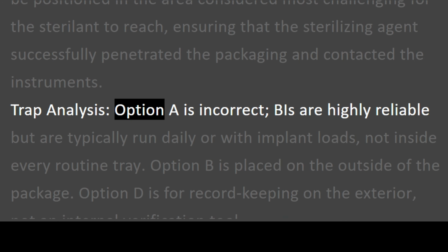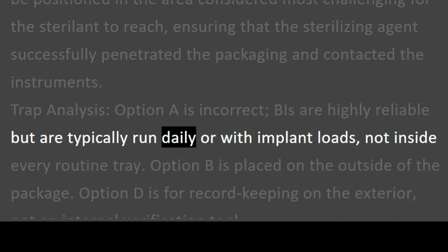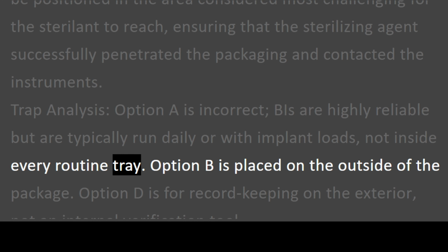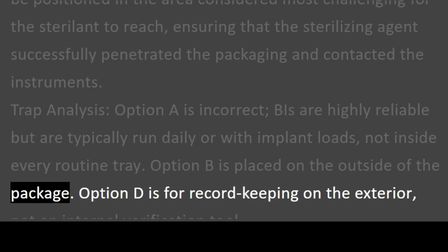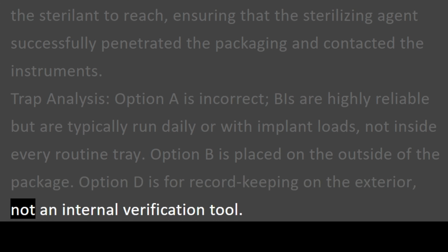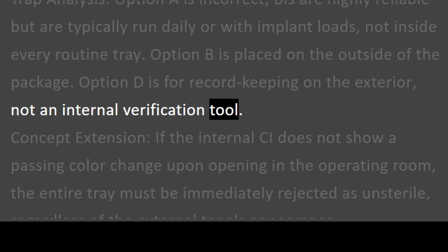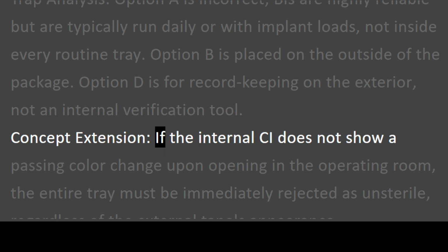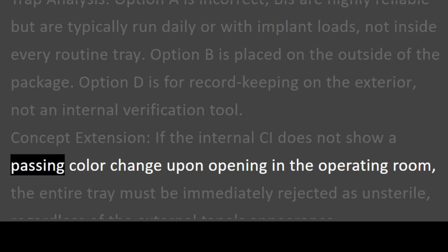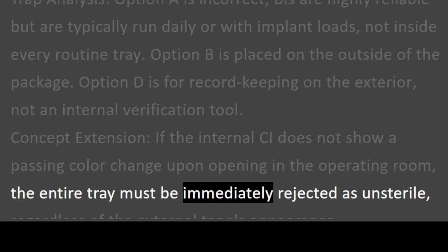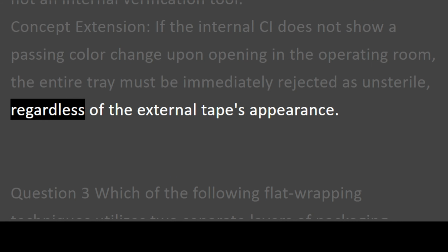Trap analysis. Option A is incorrect. BIs are highly reliable but are typically run daily or with implant loads, not inside every routine tray. Option B is placed on the outside of the package. Option D is for record keeping on the exterior, not an internal verification tool. Concept extension. If the internal CI does not show a passing color change upon opening in the operating room, the entire tray must be immediately rejected as unsterile, regardless of the external tape's appearance.